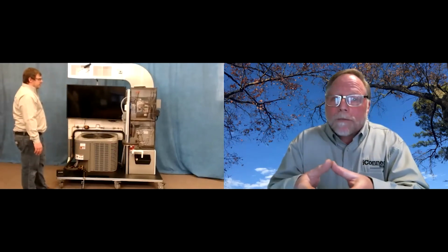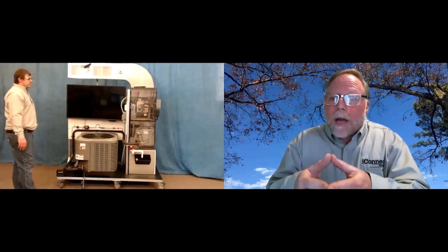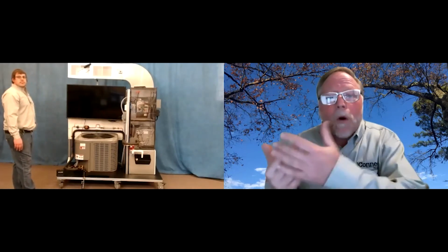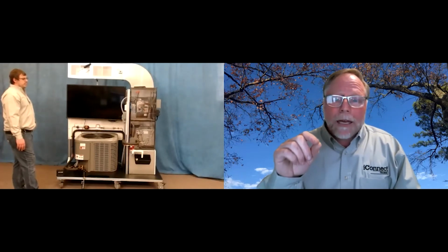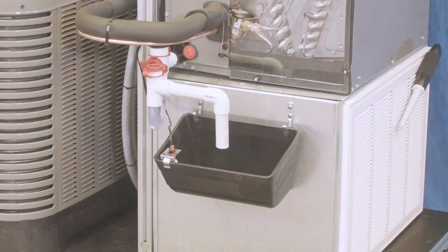So it is important that we have a deep enough trap so that when it starts trying to fill it with water, we just don't pull that water back up out of the trap. So that trap is a specific dimension. It's also a very common trap called an EZ trap that is on a lot of air handlers out there, and it's got a safety in it. That way, if that trap begins to plug up and no longer drains water, that safety will take the system off before it fills up with water and spills out into a conditioned space in a basement or into the auxiliary drain pan.